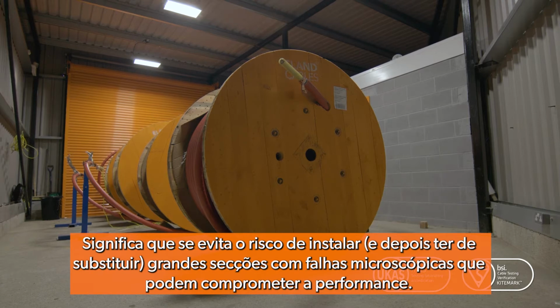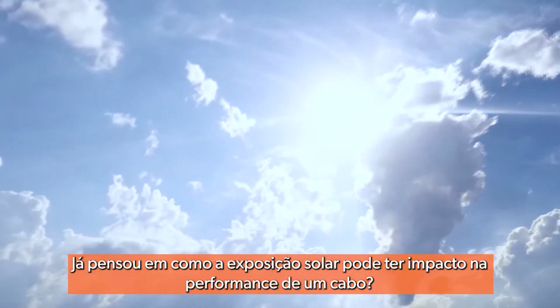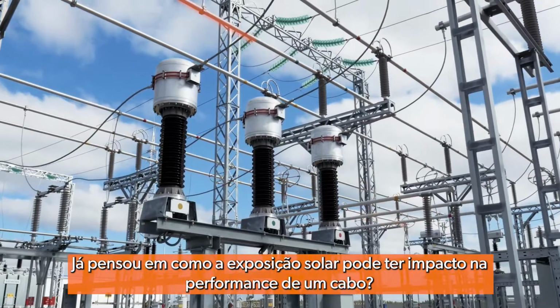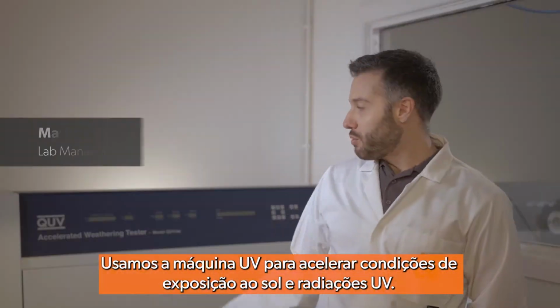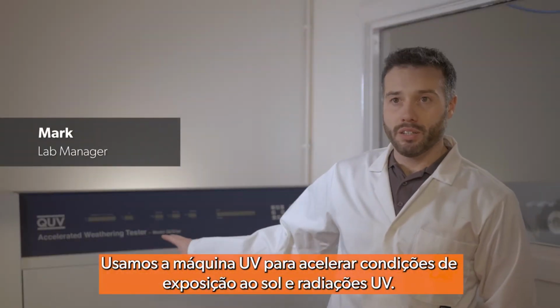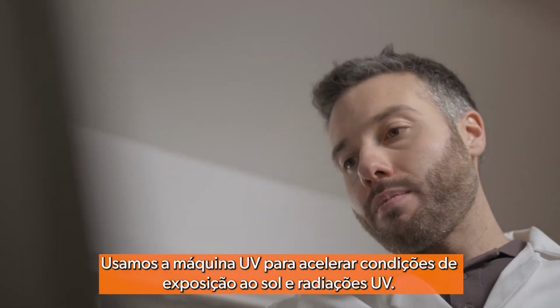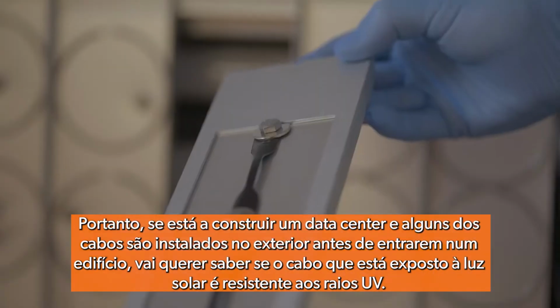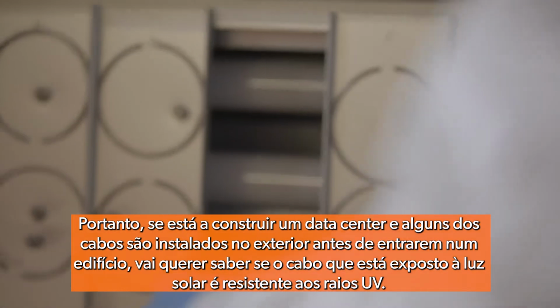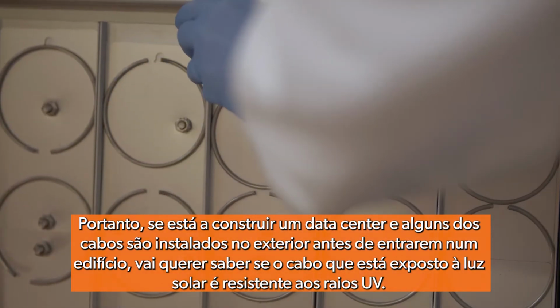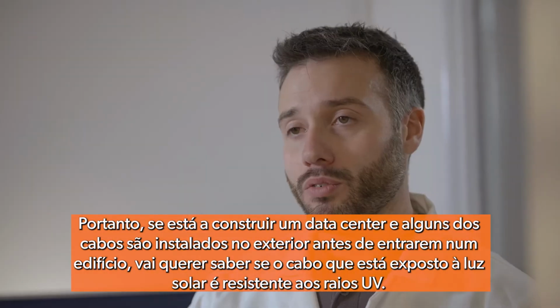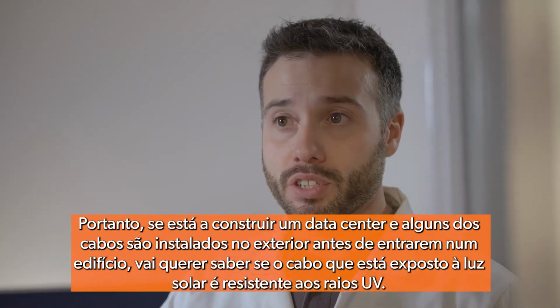Have you thought about how exposure to sunlight can impact a cable's performance? We use the UV machine to accelerate exposed conditions such as sunlight and UV radiation. So if you're building a data center and some of the cables are installed externally before coming into a building, you want to know that that cable that you've got exposed to sunlight is UV resistant.